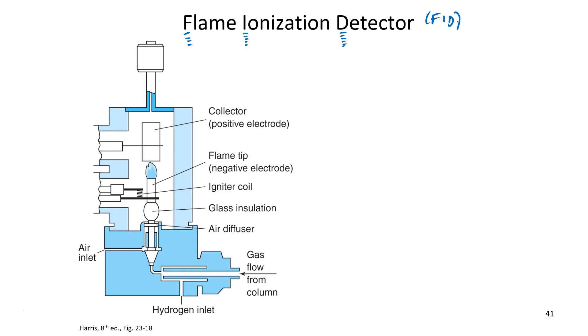Here is a nice diagram of the FID. Notice that you have gas flow from the column. And what does that encounter? Sure enough, it actually does encounter a flame. Notice that we're also using hydrogen as fuel for the flame.